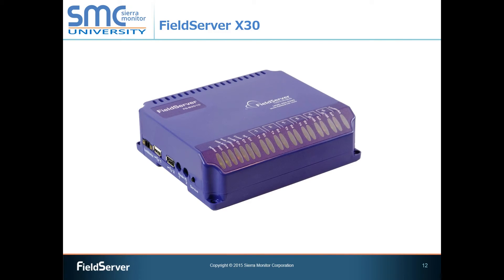Our other platform is the FieldServer X30, which comes standard with two Ethernet ports, two RS-485 ports, two RS-232 ports, and a LonWorks port. Additionally, it is possible to add an option card to this platform in order to support other protocols that use their own chipset design. Examples of these protocols are Profibus, DeviceNet, and ControlNet. The X30 platform supports point counts of 1,000, 5,000, and 10,000 points, and the power supply is included with the unit. You can also purchase the optional DIN rail mount, but a wall mount option is available at no extra cost.